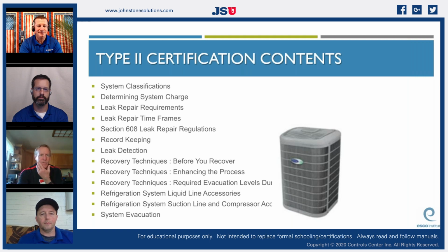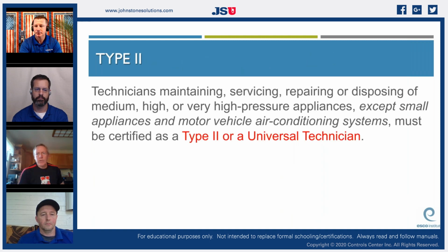So here's some of the things we're going to go over. The different ways to determine the system charge, leak repair requirements, leak repair timeframes, the regulations, which a lot of these will be dependent on how much refrigerant they hold. And we'll discuss that here in a few minutes. So technicians maintaining, servicing, repairing, or disposing of medium, high, or very high pressure appliances, except for small appliance and MVAs, which is motor vehicles, must be certified as Type 2 or universal. And universal is what we're looking to get everybody.